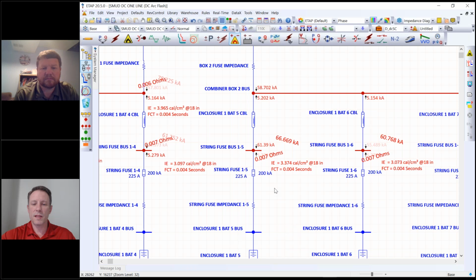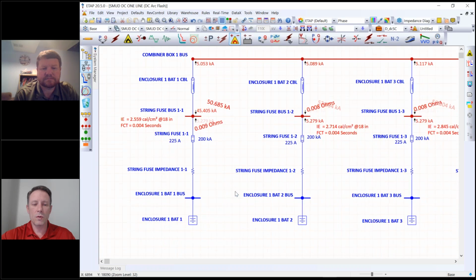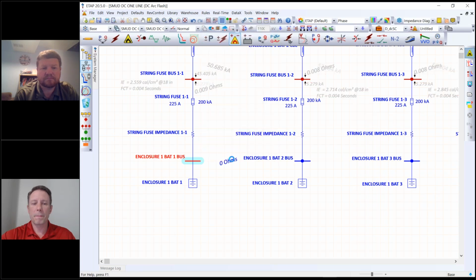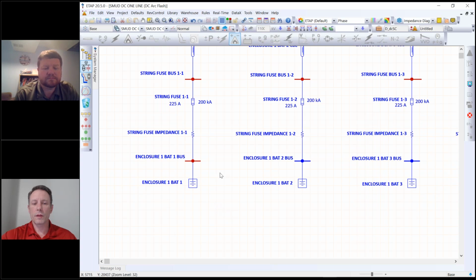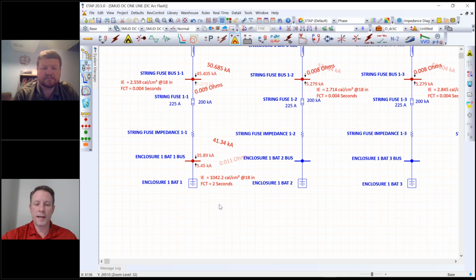Down here, a little bit closer to the battery itself, I see about 3 cal. That's still not bad. So let me fault the bus down here and see what it is at the battery. So again, at the battery, there's no protection here. So we get 2-second fault clearing time, and ETAP is showing 1,000 cals here, which is not realistic. Likely what's happening is ETAP's taking the 5K from the battery and the 35K from the other batteries and just adding it up to 2 seconds.